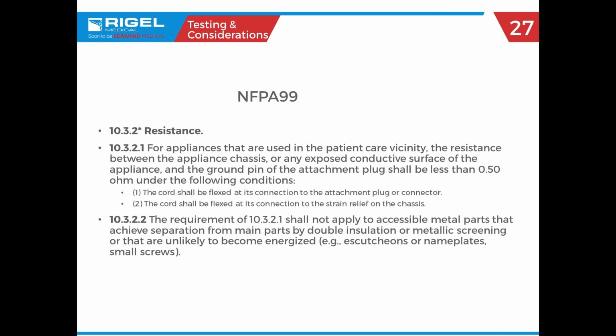Okay, this slide's a little bit busy, but basically it's just saying that NFPA 99 states that the resistance level you measure must be less than 0.5 ohms. It also states that if the device you're testing has a detachable cord, you really need to wiggle it around some at both ends, just to make sure there aren't any loose connections that could potentially affect the readings.